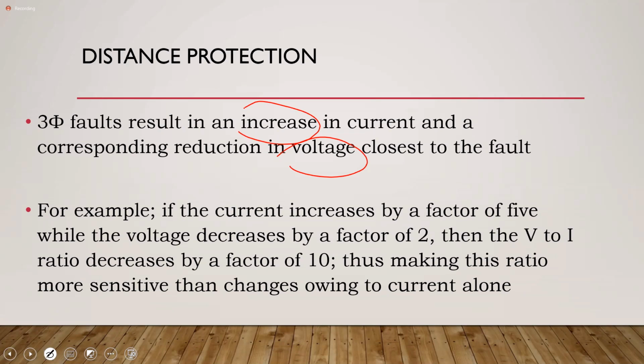So the common point, or where constant, that will be a set point. And what we are saying is, if you have a fault on the line, then your current increases, your voltage falls, and therefore that ratio gets smaller. All right? So the reverse is true for your distance relay as against your overcurrent. Because the overcurrent relay will trip if the current exceeds a certain value. For your distance relay, it means that if the ratio is less than a certain value, then it will trip. All right, so that's the difference in the principles.